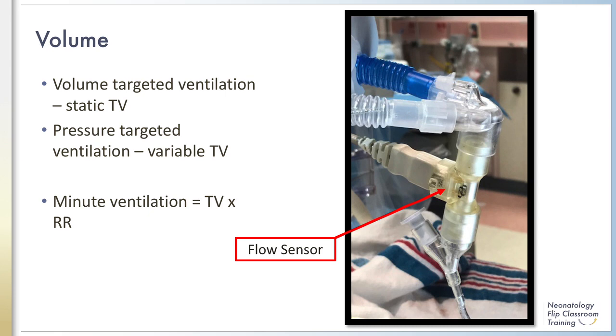A volume of gas is delivered to the patient with each inspiration, whether the inspiration was generated by the machine or the patient. During volume-targeted ventilation, the volume delivered to the patient is static regardless of lung compliance. With pressure-targeted ventilation, the volume delivered with each breath is variable depending on lung compliance. With the use of flow sensors, both the inhaled and exhaled tidal volume can be measured, and the difference between them is used to calculate the percent of endotracheal tube leak.